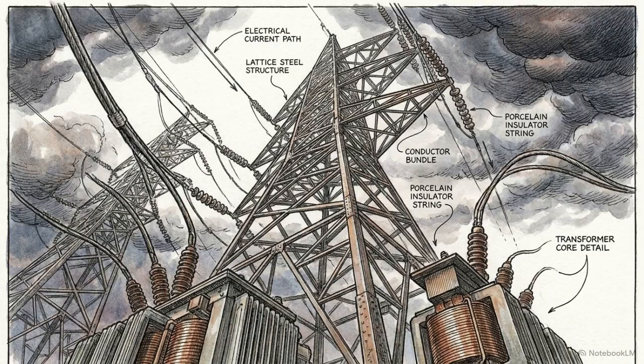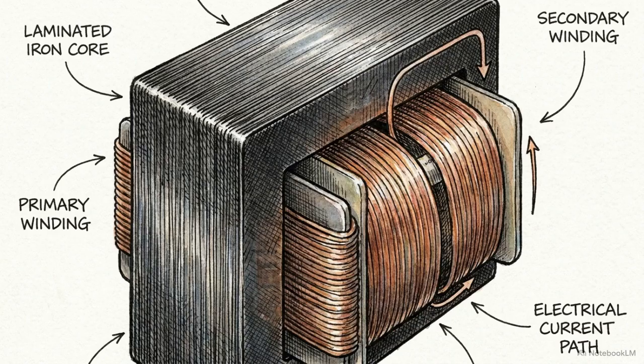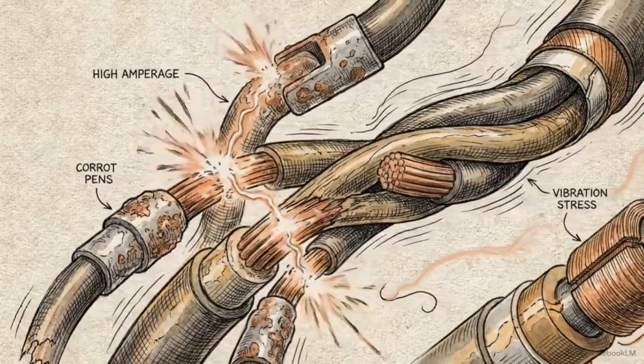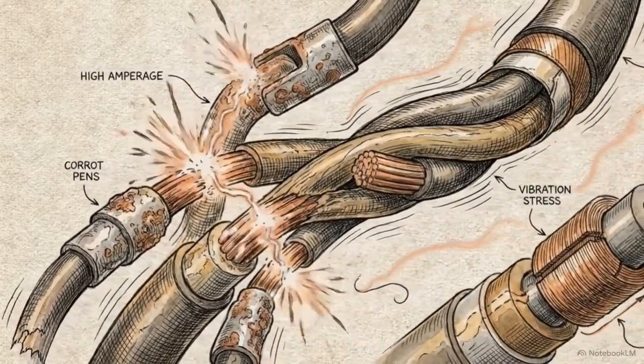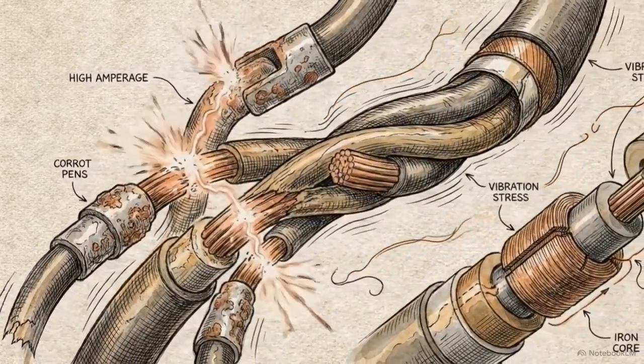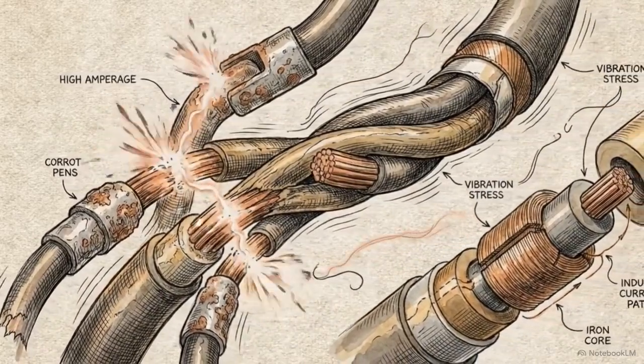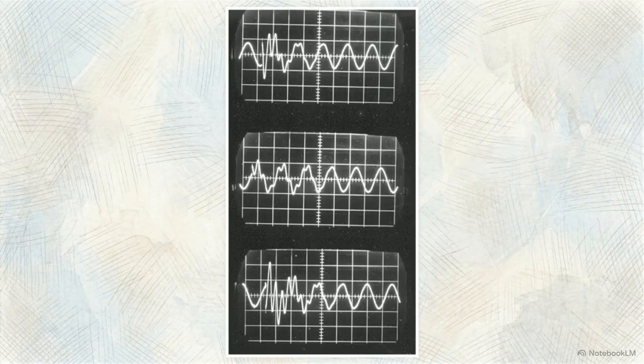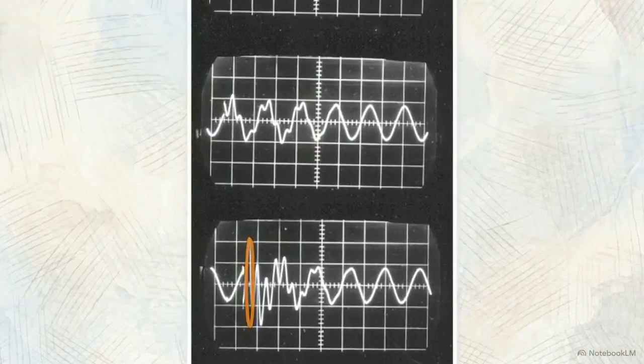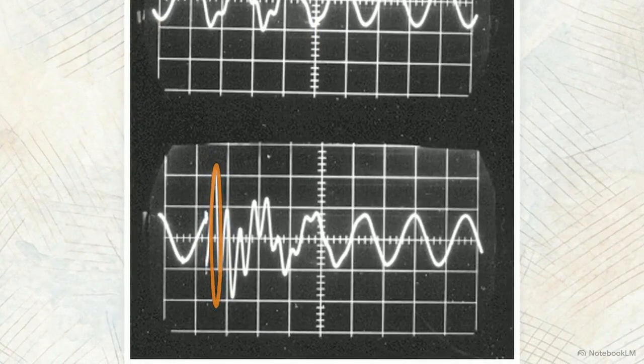The solar storm did not need to physically break the transmission lines. It only had to alter the magnetic properties of the iron cores the grid relies on to function. Because the transformer core can no longer handle the power smoothly, the blocked AC energy is forced into new, jagged frequencies, known as harmonic currents. This recording shows the result. The expected smooth 60 Hz sine wave is replaced by second, third, and fourth order harmonics. These spikes represent extreme electrical distortion.